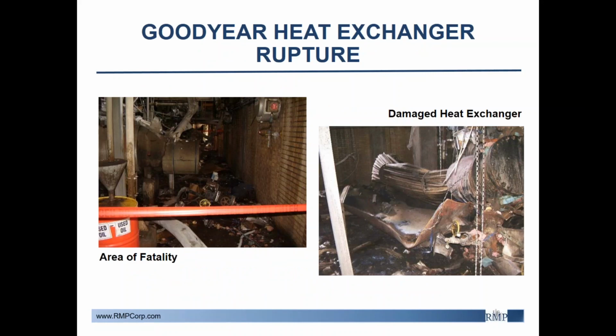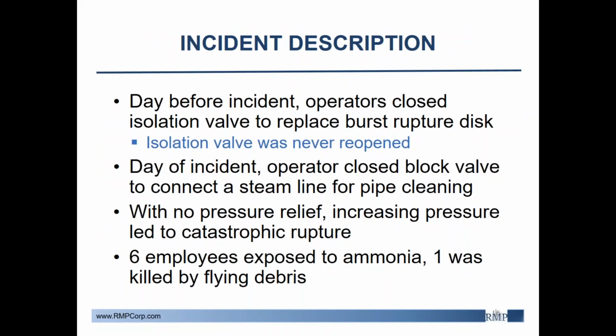The next incident I'm going to cover is an accident that occurred on June 11, 2008 at a Goodyear tire company. A heat exchanger ruptured and tragically killed an employee and injured 6 others. Pressurized anhydrous ammonia was used in the heat exchanger to cool chemicals used to make synthetic rubber. The day before the incident, operators closed an isolation valve located between the heat exchanger shell and the relief valve in order to replace a burst rupture disc. The rupture disc was successfully replaced, but the isolation valve was never reopened.